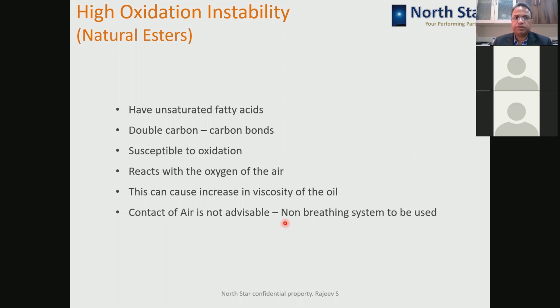So that is one limitation of natural esters. You have to go for non-breathing transformers only. It means either it should have an air cell mounted in the conservator, or it should be hermetically sealed, where there is no breather, and such a transformer is totally isolated from the external environment. In such transformers, you can very well use natural esters. Other than this one limitation, natural ester is much more superior compared to mineral oil, and also, as I said, up to some extent with synthetic esters also.